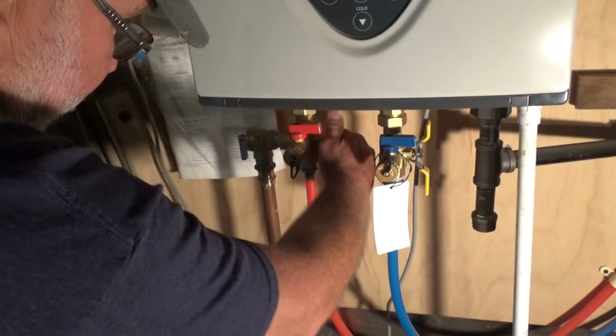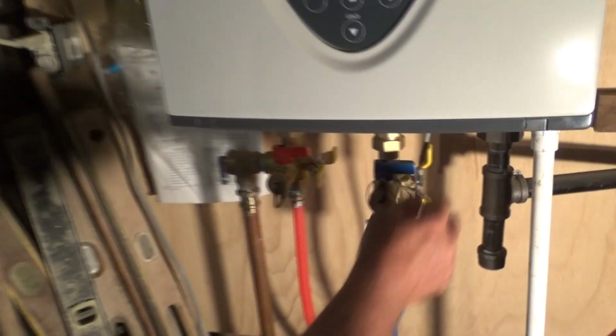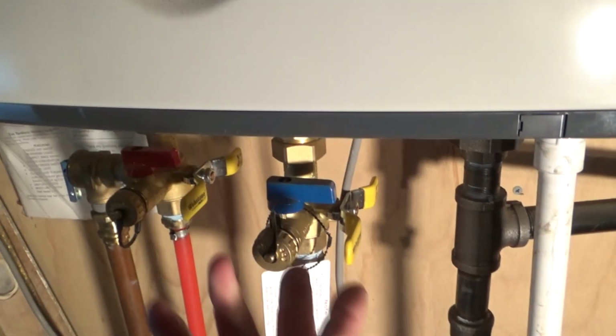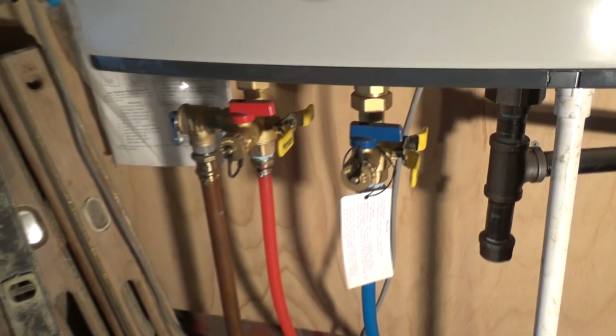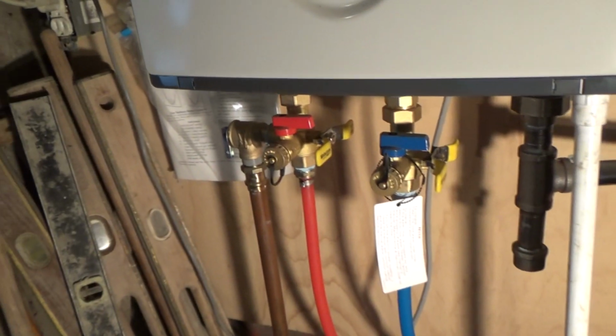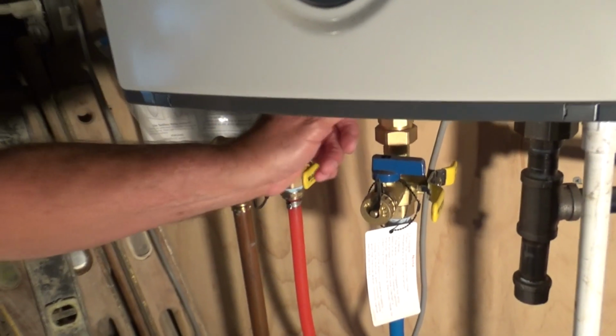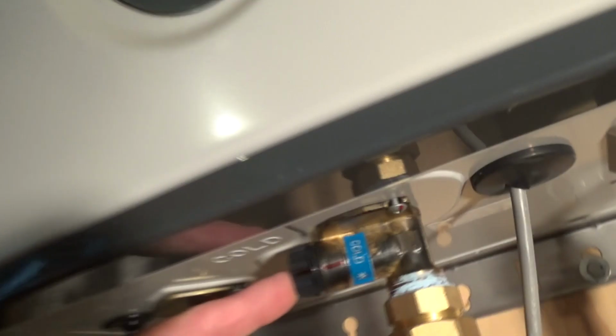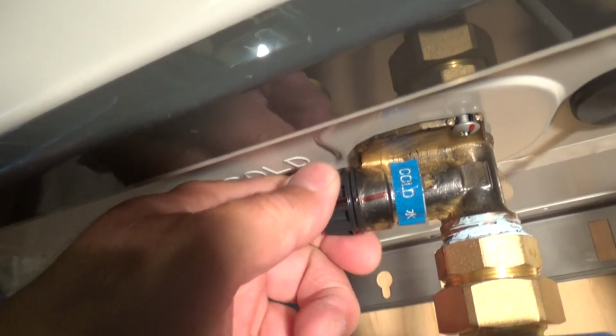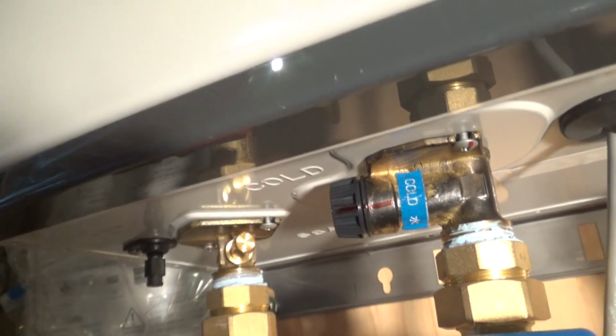Alright, we'll shut this off. These are the service valves. Some guys don't put the service valves on, but I put them on so we could flush the heat exchanger out. There's a little filter up in here. Sometimes when I run the solution through, I have to take it out because it'll clog up and the pump won't work. So if the pump stops working, I'll have to take that out.